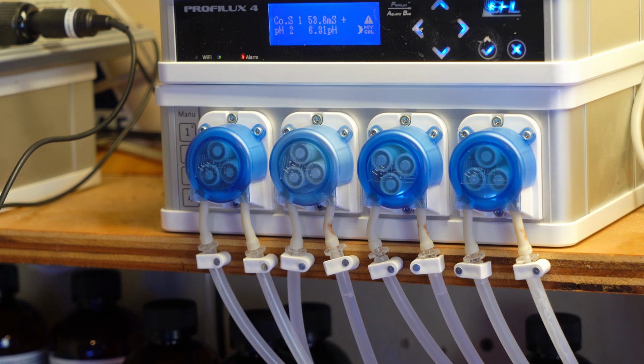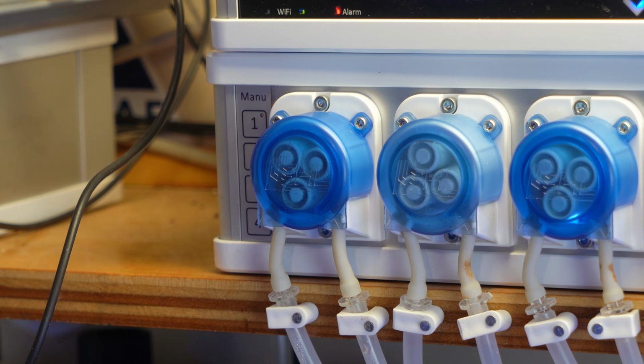So other than that, the features are pretty much the same. Let's get into the maintenance for the Doser 2.1 and 2.2. I do my major maintenance routine every 3 months, but it does matter in terms of how often the peristaltic dosing pump heads are used. If you're dosing like 5 mLs per day, you won't have to do as much maintenance as often as if you're dosing 100 to 150 mLs per day. Just want to make that clear.